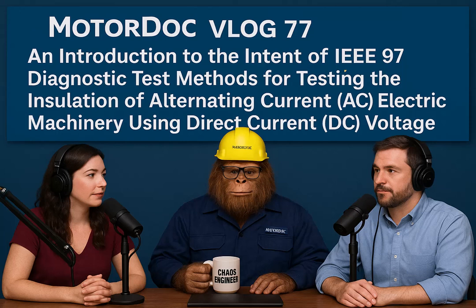Precisely. You isolate it from those continuous conduction currents, which, as we said, are often heavily influenced by external factors like surface contamination or bulk moisture leakage. So the depolarization current is particularly valuable for looking at the internal condition of the insulation itself, kind of free from that surface noise. You got it. By analyzing the depolarization current, you gain insights into the intrinsic behavior of the insulation material itself, its health, its aging.